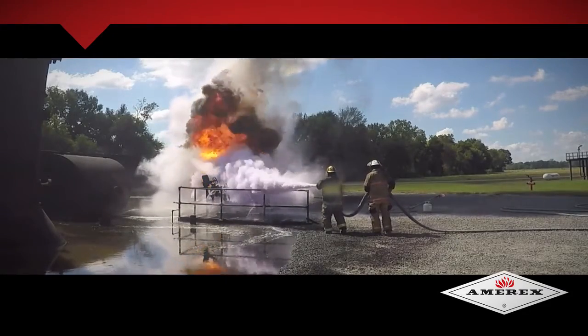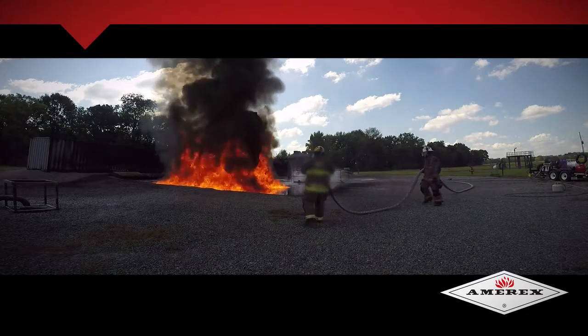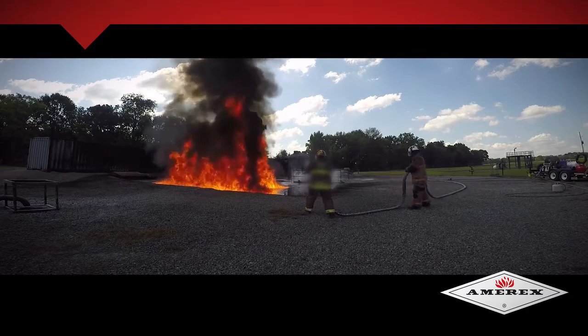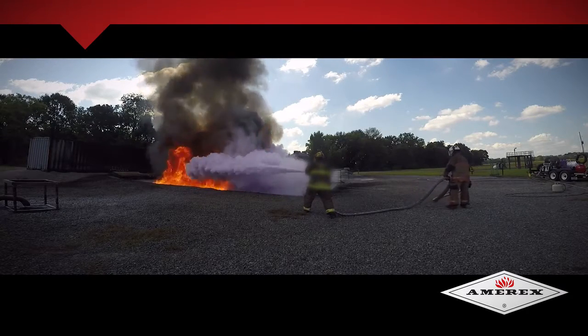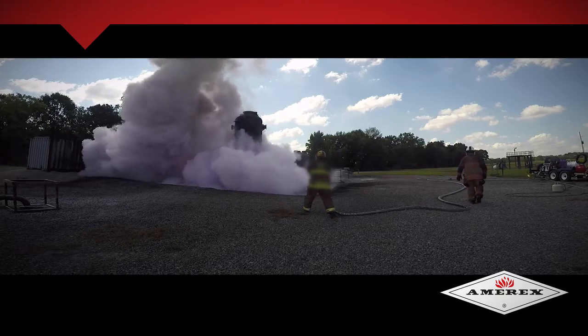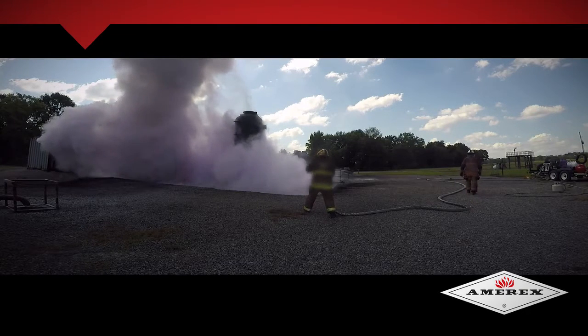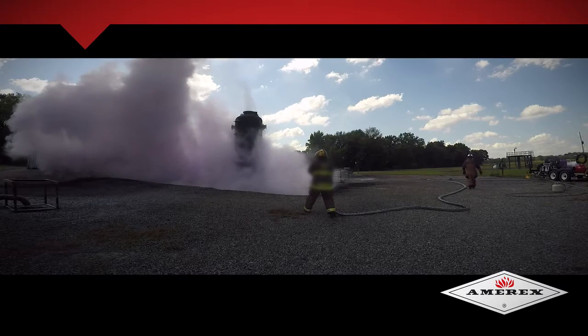Amerex Dry Chemical Systems attack the chemical chain reaction aspect of the fire tetrahedron. Its thick layer of powder coats the surface to which it is applied, effectively cutting the fuel off from its oxygen source and eliminating the chemical chain reaction. Amerex Dry Chemical Systems are unique from any other system on the market. The expulsion system allows each hose reel to obtain dry chemical through independent discharge tubes, affording a constant discharge rate on demand, allowing variable installations with isolated discharges.